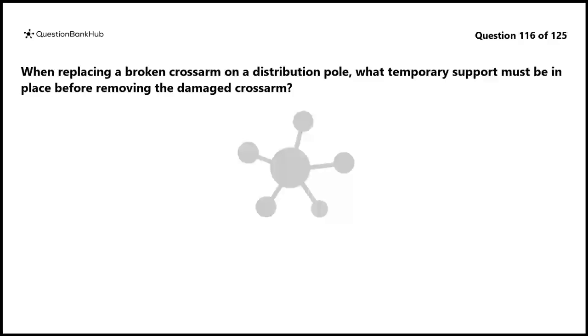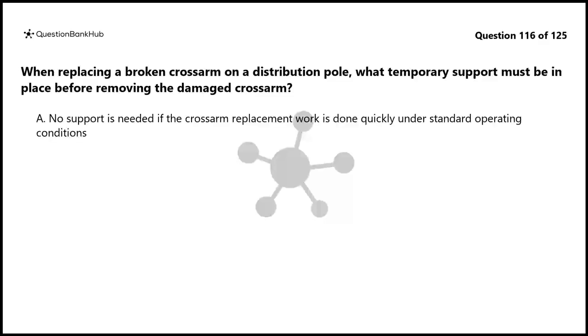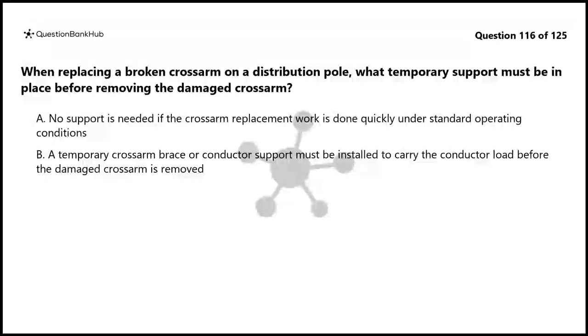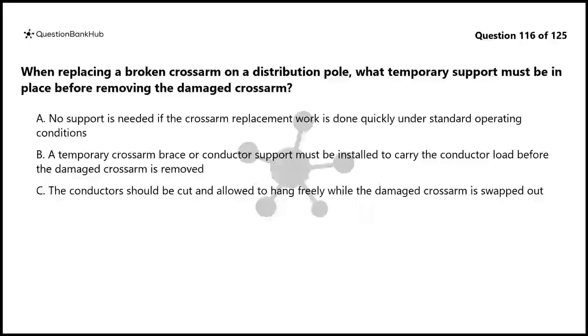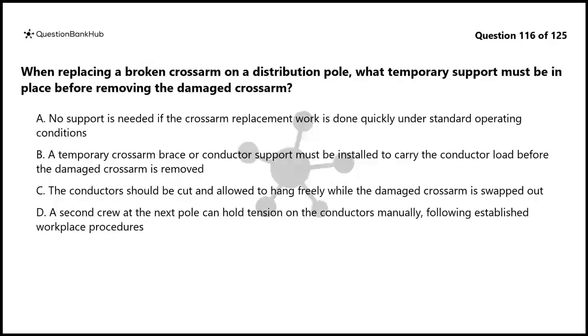Question 116. When replacing a broken crossarm on a distribution pole, what temporary support must be in place before removing the damaged crossarm? A. No support is needed if the crossarm replacement work is done quickly under standard operating conditions. B. A temporary crossarm brace or conductor support must be installed to carry the conductor load before the damaged crossarm is removed. C. The conductor should be cut and allowed to hang freely while the damaged crossarm is swapped out. D. A second crew at the next pole can hold tension on the conductors manually, following established workplace procedures.